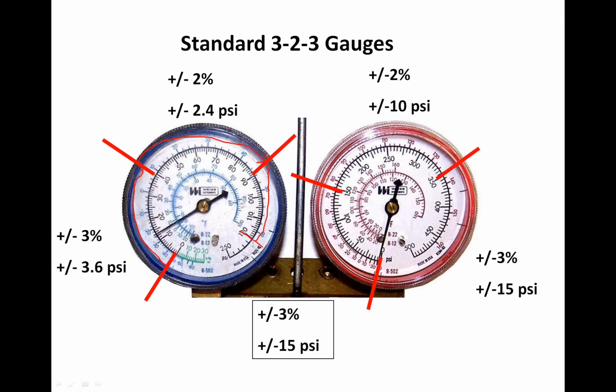Now, if we're talking 410A gauge, this is the reason we don't want to use this R22 gauge for 410A. It's not just because of the higher pressure, but it's because this gauge will not read accurately at the top end of its span. It's designed to operate in the center of its span. We'll get a high side gauge, right where we'd be at the center here of the high side gauge. We're at plus or minus 10 psi. Okay, and that's a brand new perfect gauge right out of the box. A brand new perfect gauge. You'd be in the center of a span where it's most accurate. It's plus or minus 10 psi.